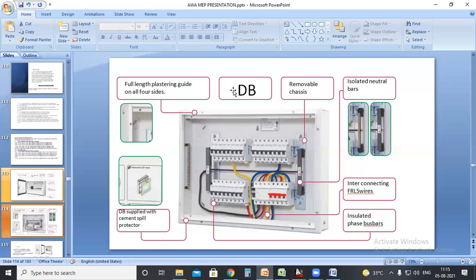But what if you need a three-phase supply? You cannot choose this distribution board. In that case, you need to select the VTPN DB, vertical triple pole neutral. That is another type, which I think is commonly used abroad. But in India, we have the main category TPN, that is this one. And for a residential building, this same DB will have a rotary switch attached to it. That is the phase selector DB, also known as phase selector DBs.